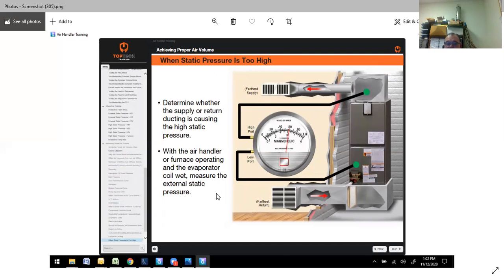Now, it is important. Guys call me all the time. Once they determine they have high static, like the EcoNets, if you deal with a communicating system, it will tell you. There's a way you can actually view what your static pressure is, and it's fairly accurate within maybe a point or two. So if it tells you it's high, you can bet it's high. At that point, you need to determine whether it's the supply issue that's the problem or the return issue that's the problem.